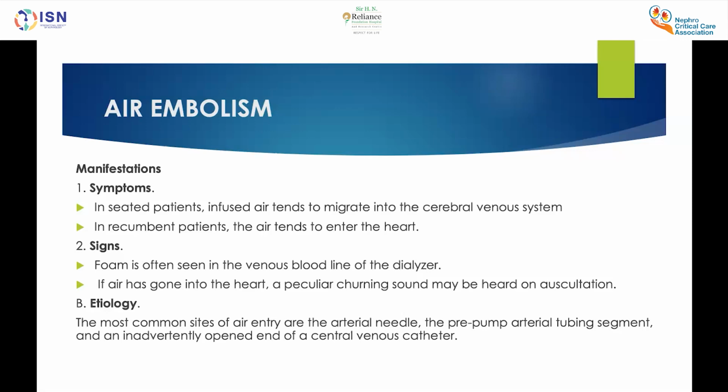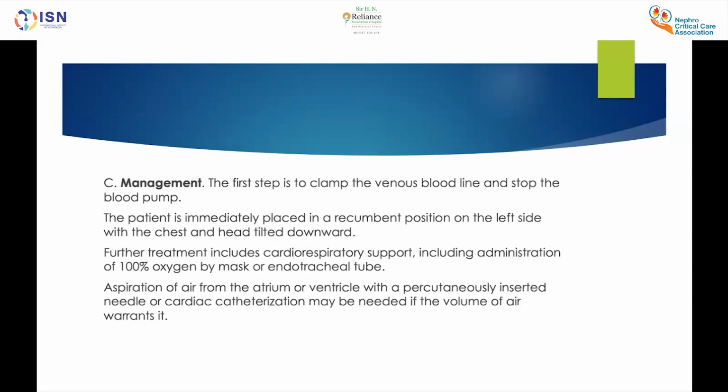And where does this enter from? The site of arterial needle insertion, the pre-pump arterial tubing segment, or an inadvertently opened end of a central venous catheter. This could be the cause of air embolism. But how do you manage that?